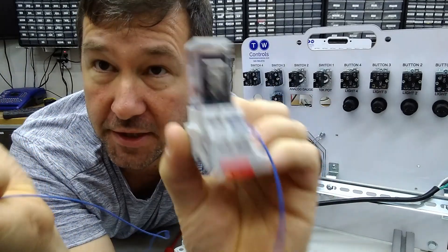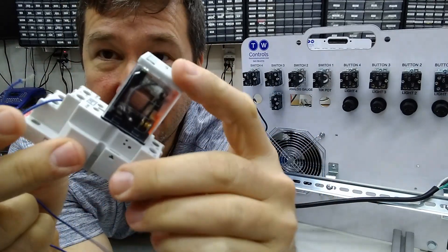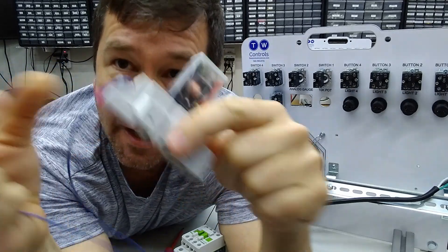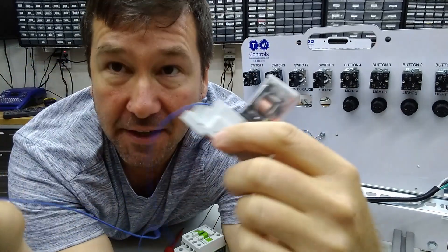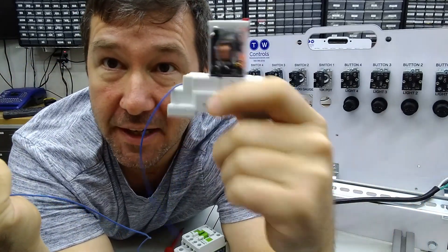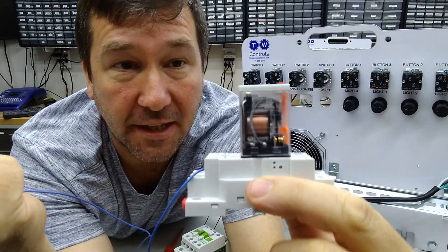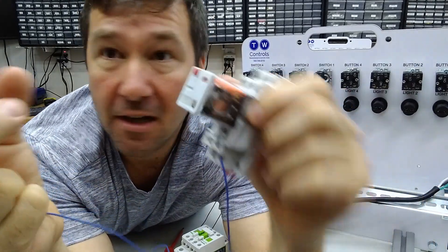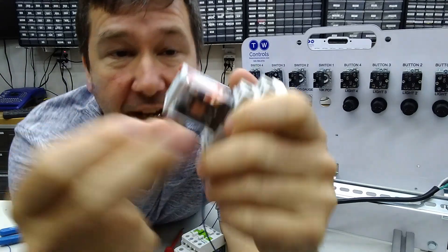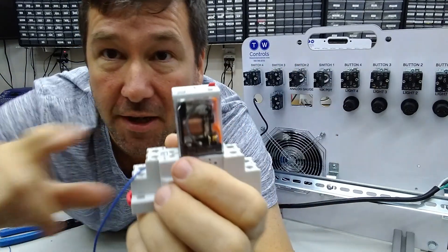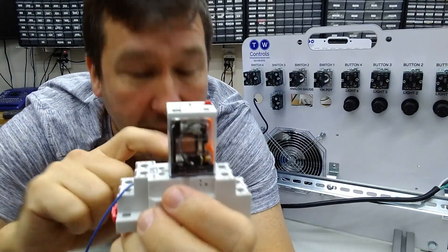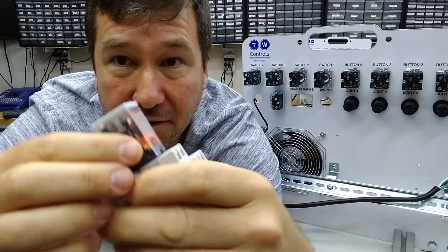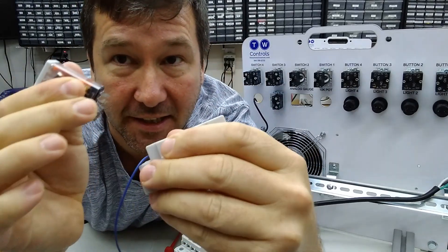Oh no, you didn't. And the reason you didn't is contactors, we talked about their contact rating, but I didn't talk about the coil rating. Every contactor or relay also has a coil voltage. And this is a 220 volt coil. And we're using 24 volt here, so this will not pull this in.